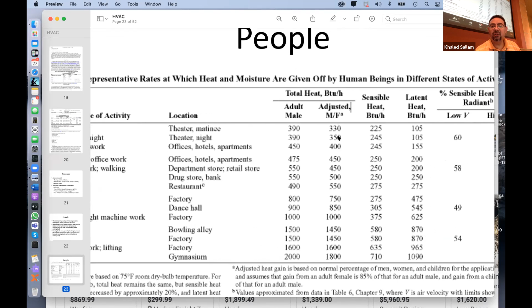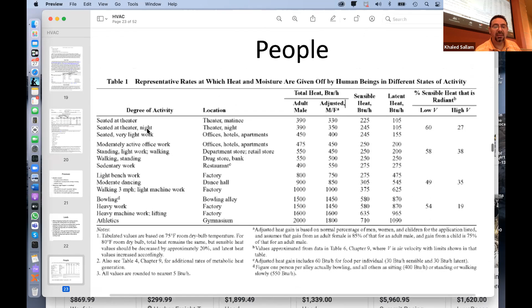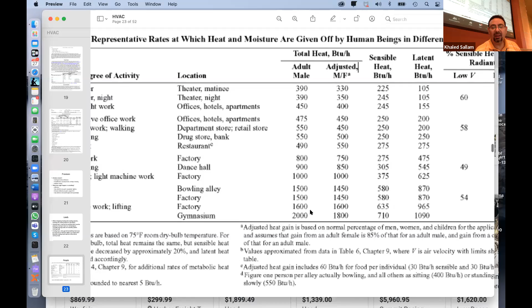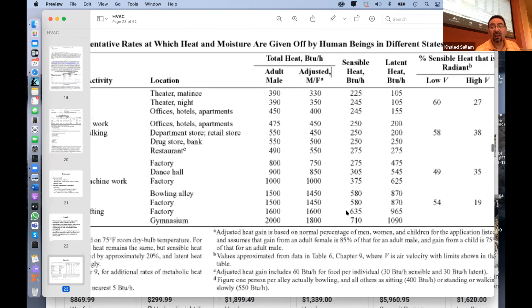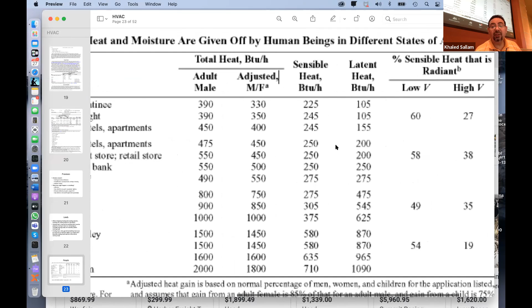Adult male, adjusted male-female ratio. And so a person seated at a theater, seated at a theater at night, seated very light work, moderately active work, walking, sedentary work. So for each one of those jobs, bowling alley, factory, gymnasium, look at the gymnasium, they can put out 2,000 BTU per hour. So you add all those total heat and also the division between sensible and latent heat.